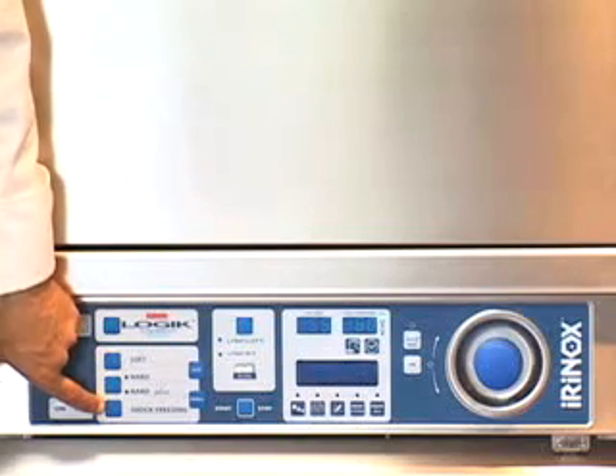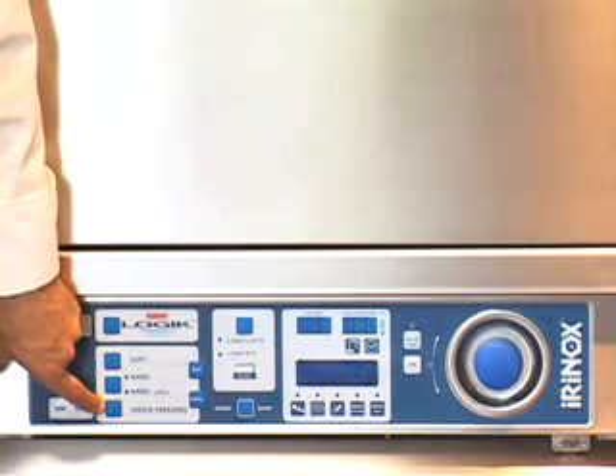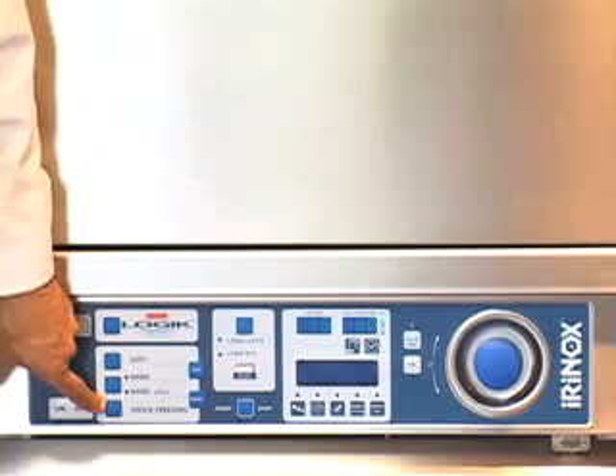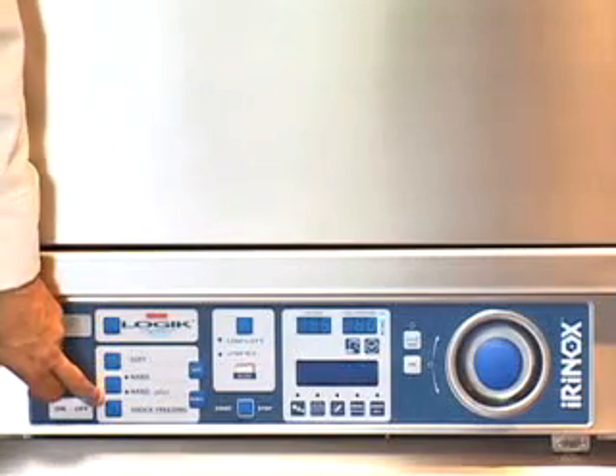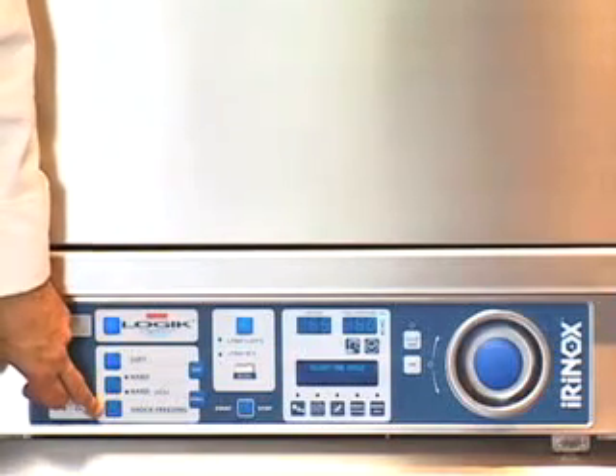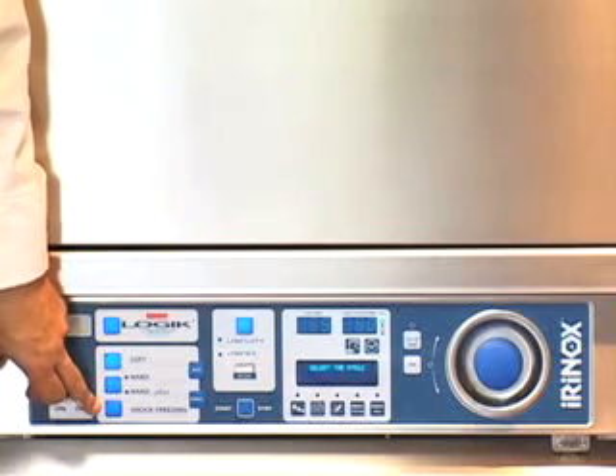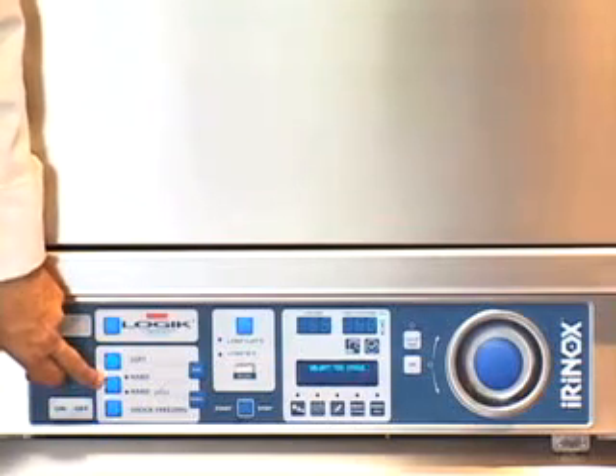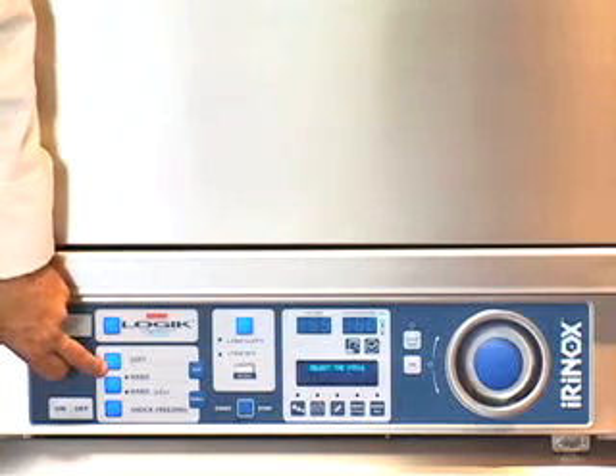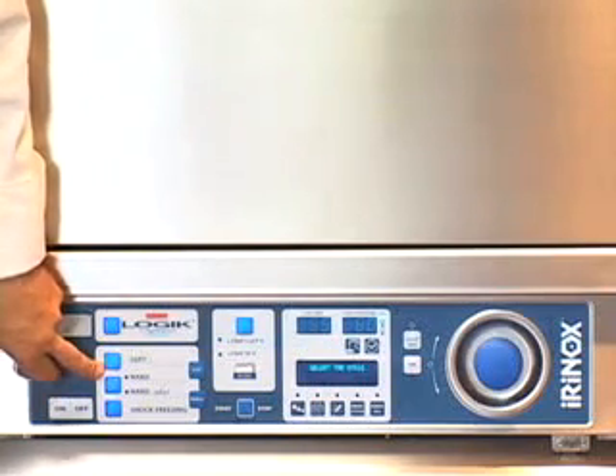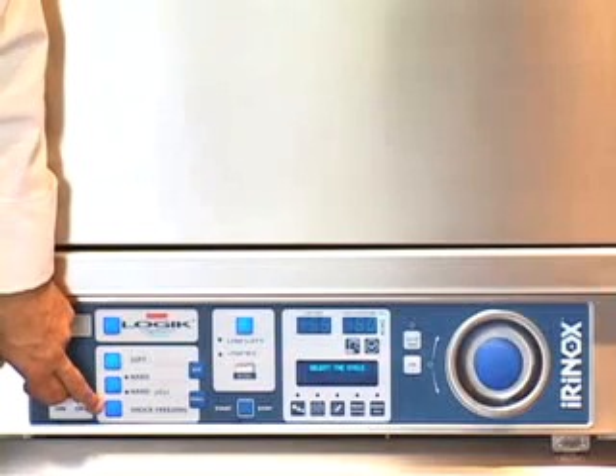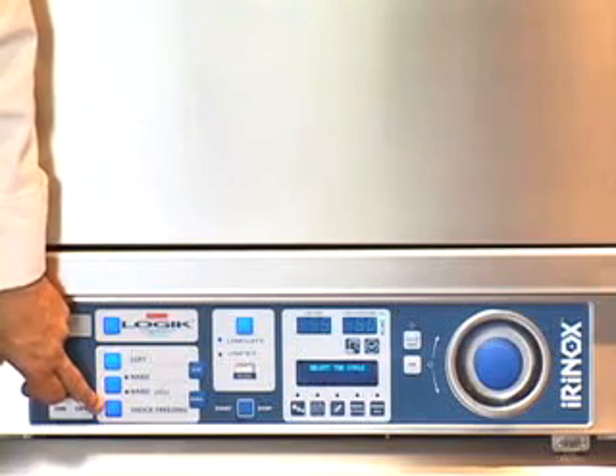The shock freeze mode is for any product that you want to take to 0 degrees Fahrenheit. All of the modes, cycles we have, are designed to take product directly from the oven at 200 degrees core temperature to either 37 degrees or 0 degrees. In the case of chilling, it will take 90 minutes in automatic, or in the shock freeze mode, it will be up to 4 hours in automatic mode.